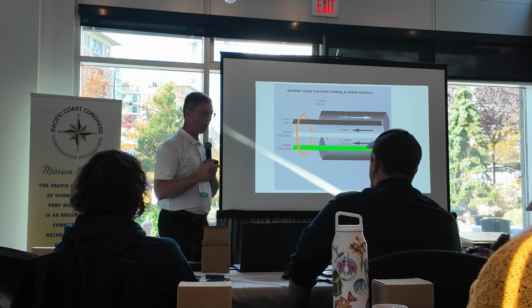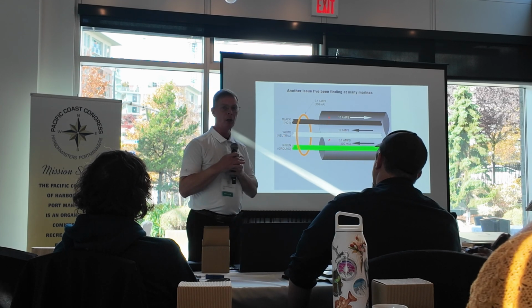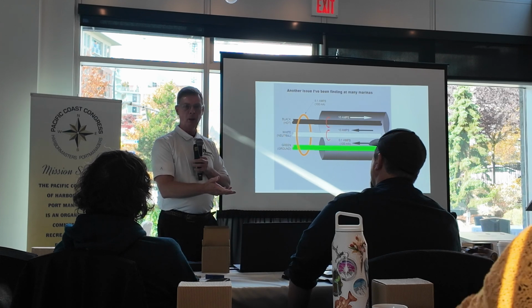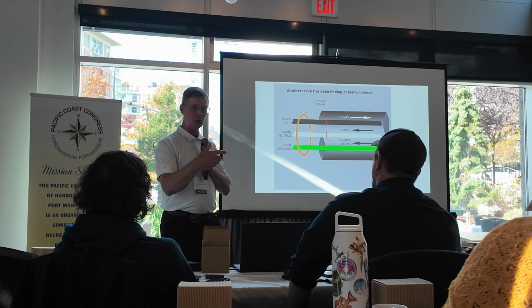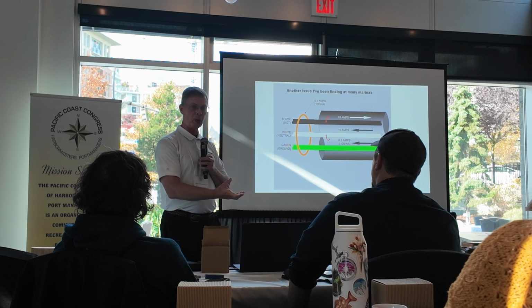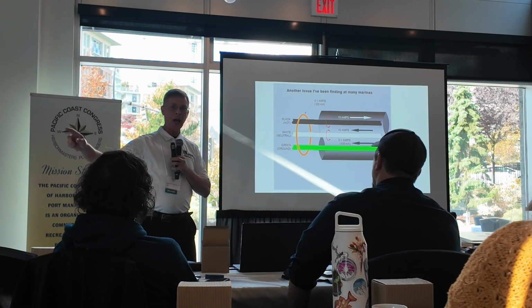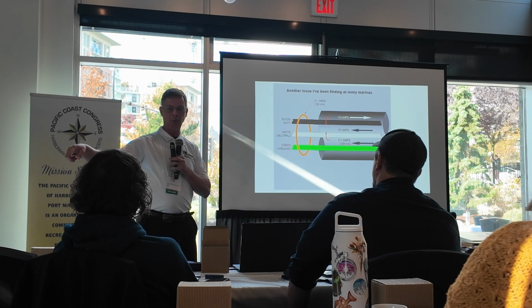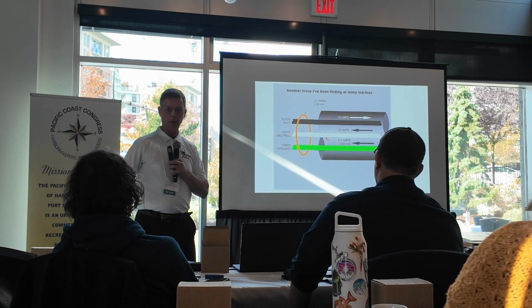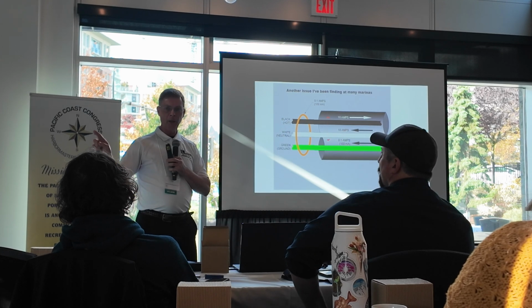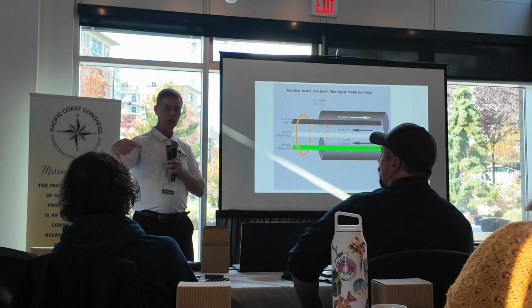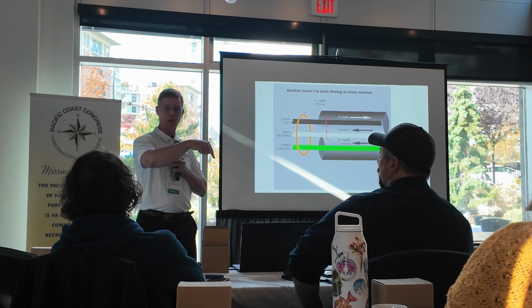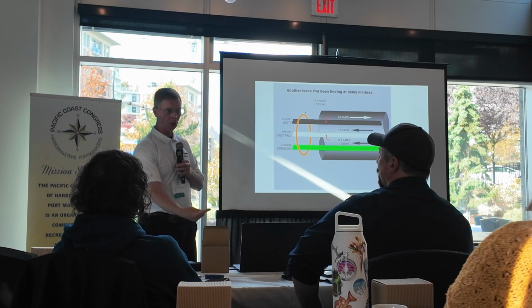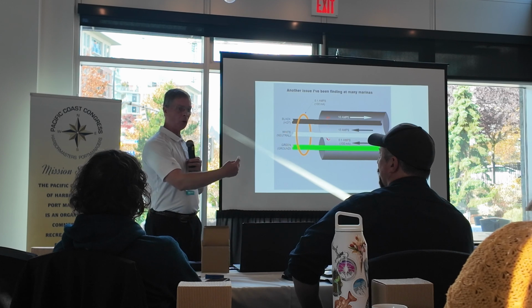And what's happening, and I've seen this several times, is I got a boat, and that boat measures 10 amps, in this case, going and coming. But I measure the ground wire, and I measure current on the ground wire. Then I go to this neighbor's boat, and I measure leakage current on his boat. And these are metal hull boats. It could be metal pontoons or metal hull boats, whatever it may be.